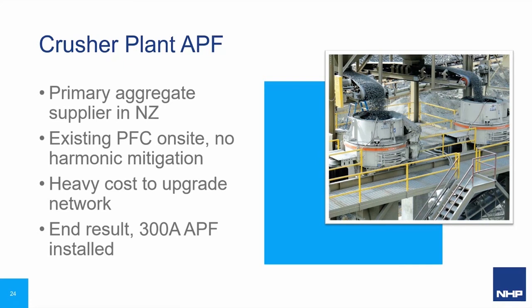Now, the site is located around 12 kilometres from the nearest electrical supply infrastructure, and it's connected by a long piece of wet string, so to speak. That is to say, the 11 kV feeder line has a very low capacity, and it's not particularly reliable either. So the quarry owners applied to the local power authority to expand the capacity of the feeder line, and they were quoted something in the order of $4 million to do the upgrade. Well, yes, it was, and the quarry owners decided to take responsibility for their own destiny, and instead, at much lower cost, installed 4 500 kVA diesel generator sets, giving a total of 2 MVA of generator capacity on site, in addition to the existing 11 kV line, which feeds a single 750 kVA transformer.